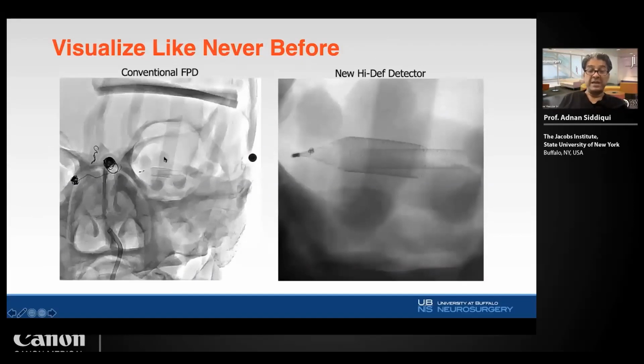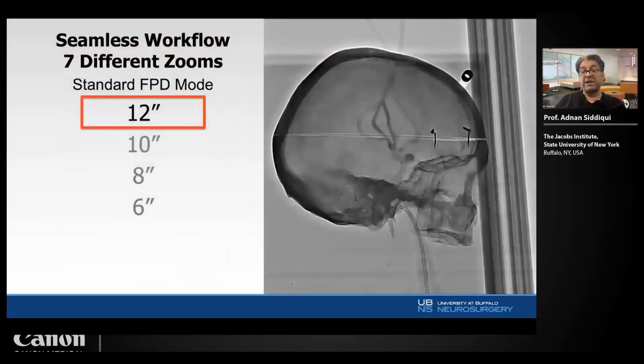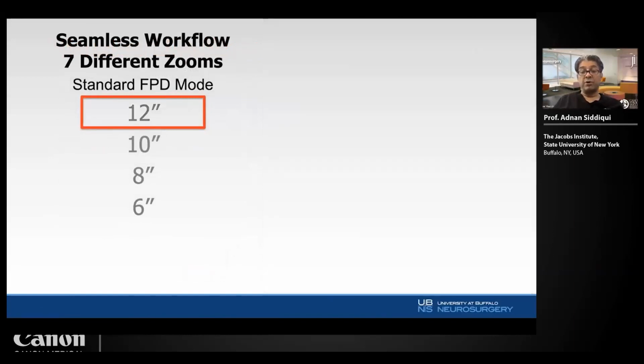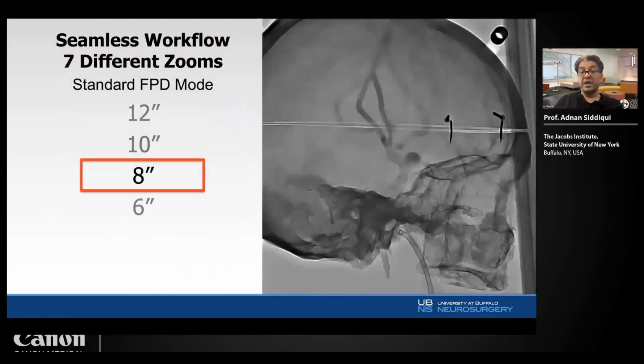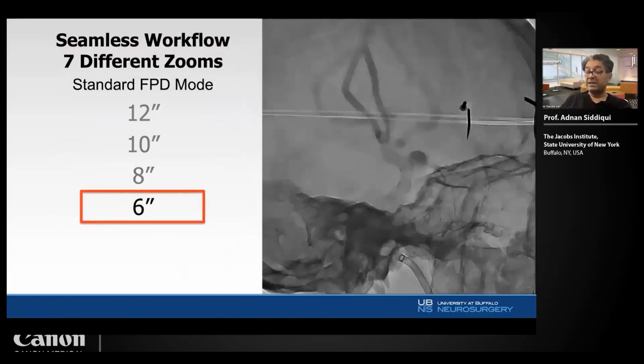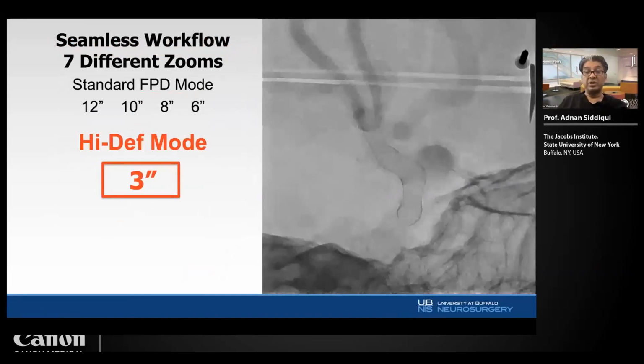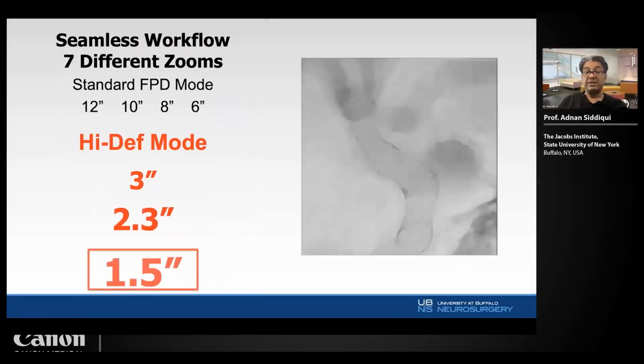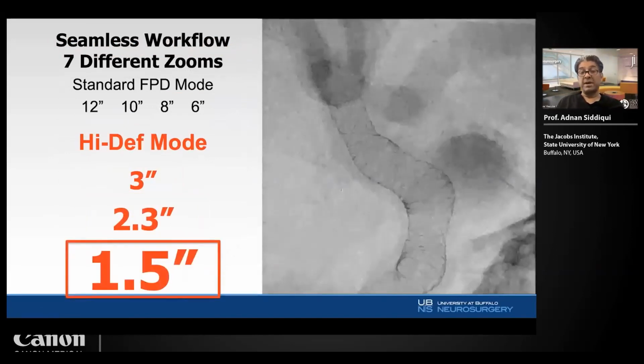This is obviously a phantom, but there you can see two braided devices, and under conventional flat panel versus high def, you can see the kind of detail that you get. So this is the standard flat panel detection of lateral fluoro, and this kind of shows you as we go from 12 to 10 to 8 to 6 inches. And that's the end of flat panel, and this is where we go into a 3-inch and then 2.3 inch. And then this is what's currently available, a 1.5 inch. So you can imagine the kind of detail one can arrive where you are seeing the platinum wires, but you're literally even seeing the chromium cobalt in there. And you can see the compression of the device in here and a little bit more maybe relaxing out here and out here. So it really allows you to visualize the device like never before.